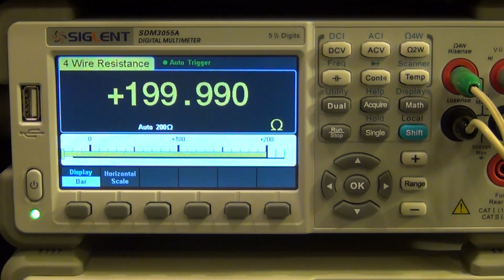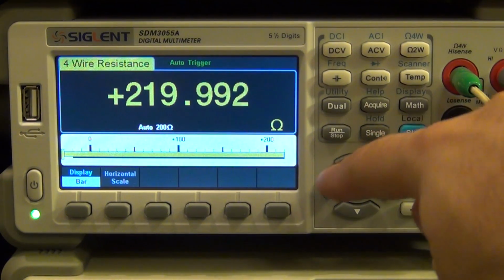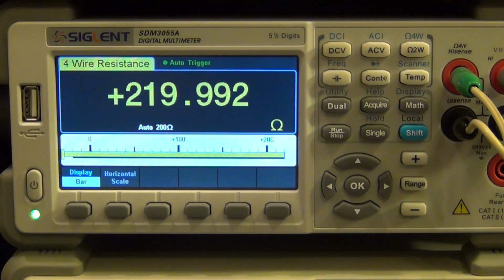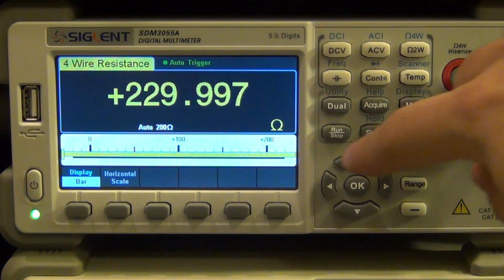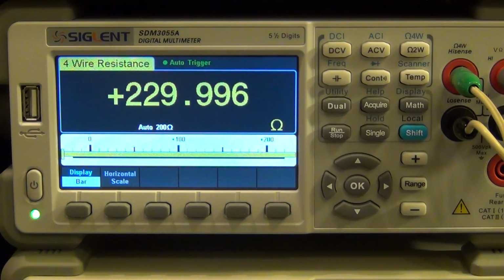Now instruments typically support going over the range by a little bit, so I should be able to go up by a couple of tens of ohms, and it still should remain in the 200 ohm range. Here we go, that's another 10, so we're sitting at 210 roughly right now. I'm at 220, you can see that we're exceeding the range right now. There we go, 230, and now it's plotting beyond the axis there. And then one more, and then 240, pretty good, still in the 200 ohm range, and one more and it should eventually switch. There it is, and it switched now to the 2 kilo ohm range at exactly 250 ohm.